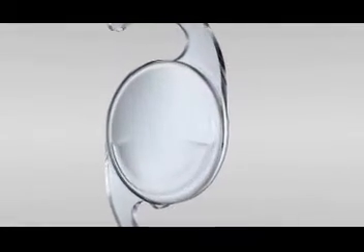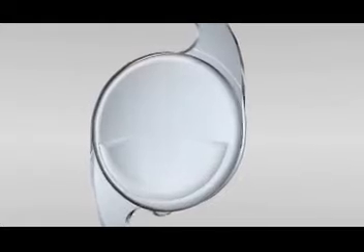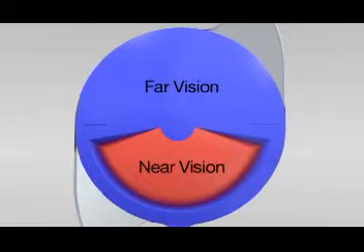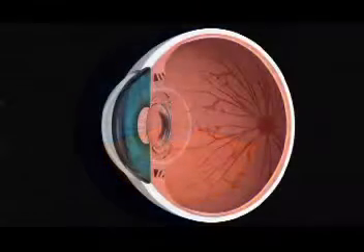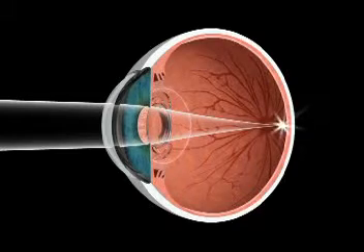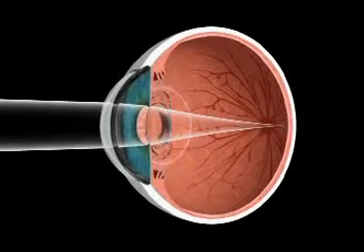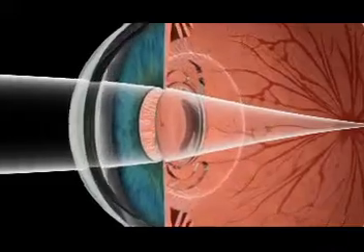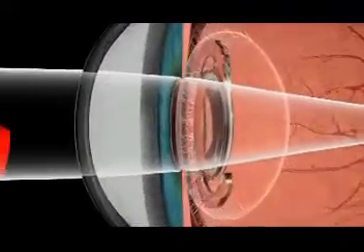The lens is semi-meridionally divided into optical sectors, creating a truly pupil-independent intraocular lens. The very steep semi-meridional transitions between the reading and distance sectors of this lens minimize reflections in the direction of the optical axis.